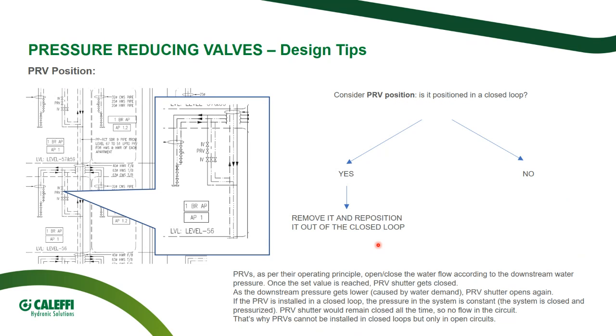The last tip we would like to give you about the pressure reducing valve is to consider the PRV position. Is the valve positioned in a closed loop? If the answer is no, there is no problem. But if the answer is yes, it is a big issue because, by their nature, pressure reducing valves will close the flow as soon as the set value is reached. So in a closed loop, you can understand the set value is always reached, so the valve will close. So I will have a lack of water and my flow rate will not be sufficient for my use and the tenants will complain. So if the PRV is positioned within a closed loop, remove it and reconsider the position outside of it.